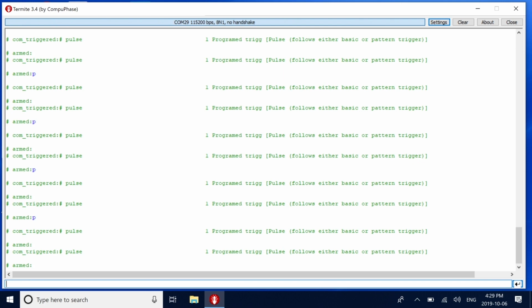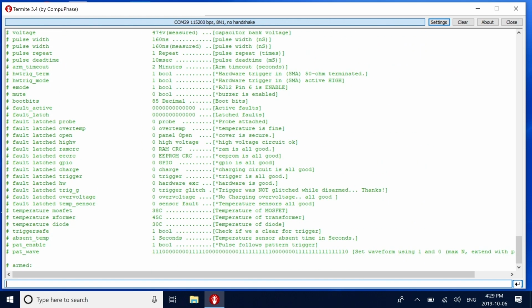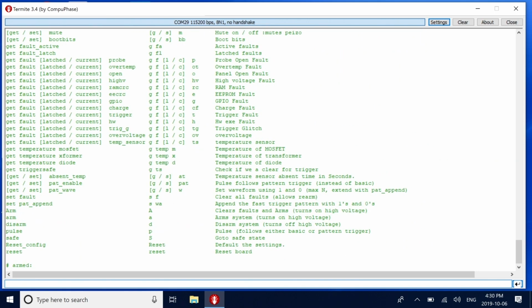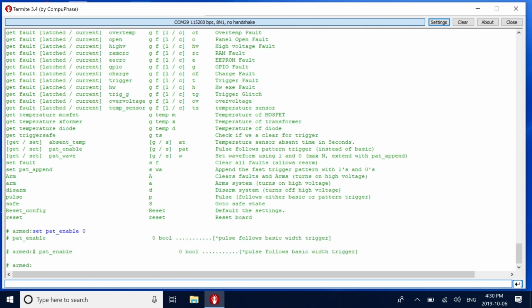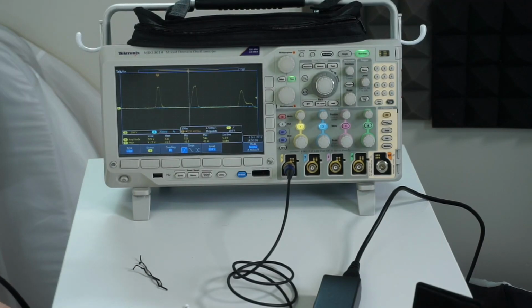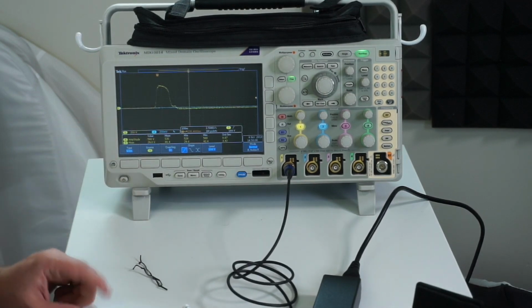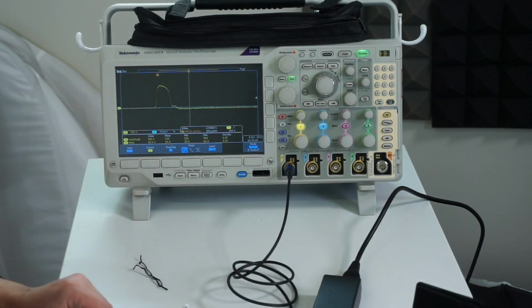What we could do too is, rather than do the pattern trigger, if we say get, we're using this pattern trigger right now. So if I say set pat enable 0, it means that it's no longer using that fancy pattern trigger. And now when I send the pulse command, it's actually going to look slightly different. Oops. There we go. So we actually see just one big fat pulse coming out of this guy.